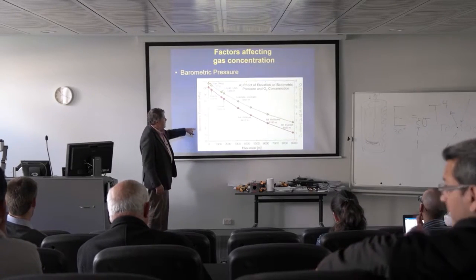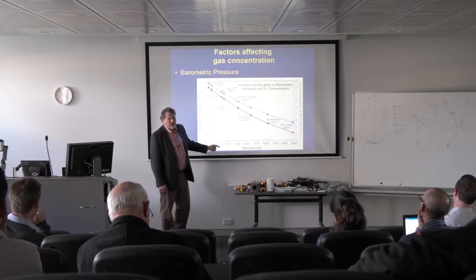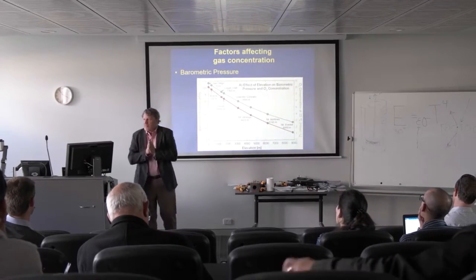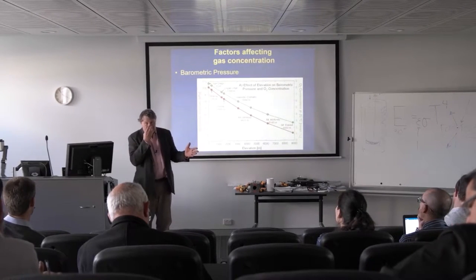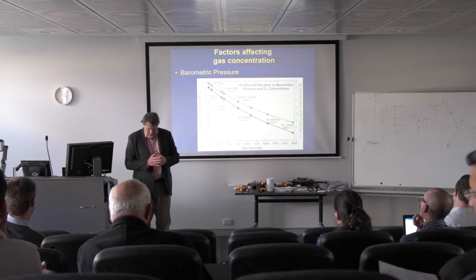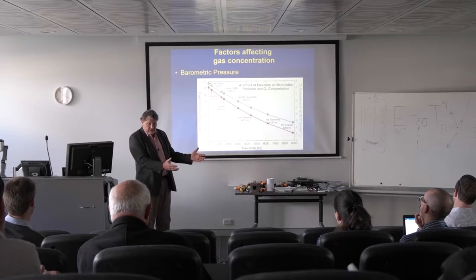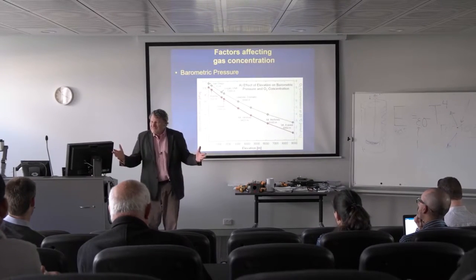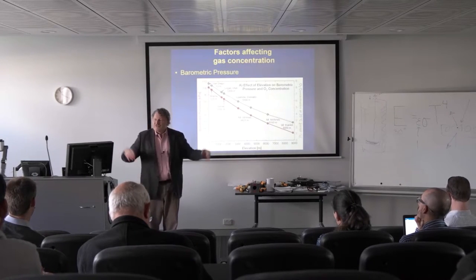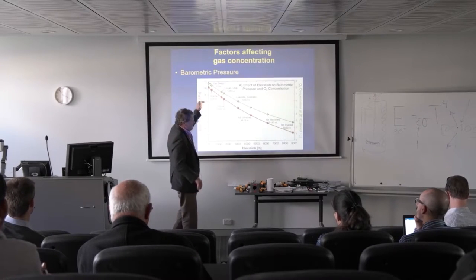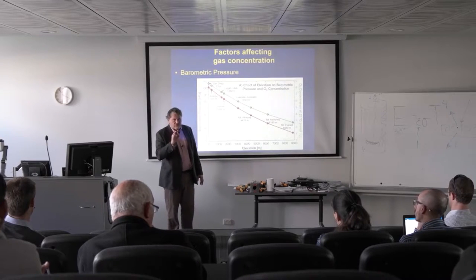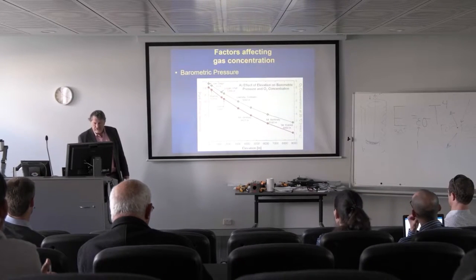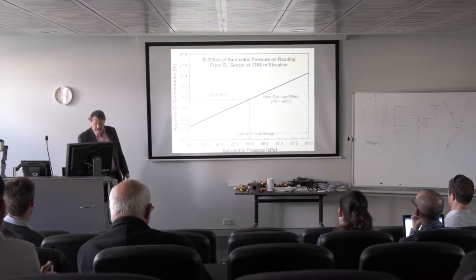Here's a great way to show it — elevation. Barometric pressure is the red line as we go up to the top of Mount Everest, and the unit on the other axis is concentration of gas. We know virtually everybody needs compressed oxygen to climb Mount Everest. But what's the percent oxygen at the top? It's exactly the same: 20.95 percent. So if it's still 20.95 percent, why do we need oxygen? Low pressure — the density of oxygen molecules is way less. This is an example of the correction for pressure. We often measure pressure alongside the gas sensor so we can correct for differences in pressure and sort out metabolism from everything else.